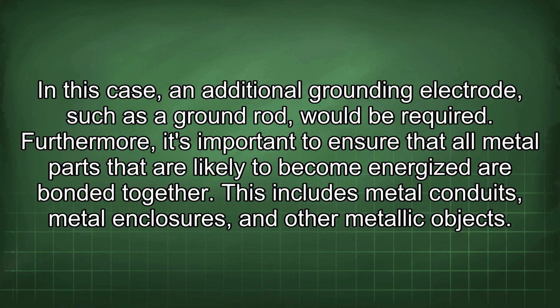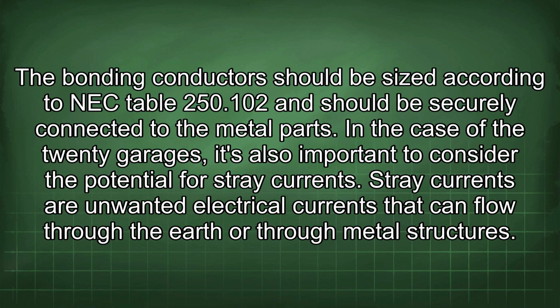Furthermore, it's important to ensure that all metal parts that are likely to become energized are bonded together. This includes metal conduit, metal enclosures, and other metallic objects. The bonding conductors should be sized according to NEC Table 250.102 and should be securely connected to the metal parts. In the case of the 20 garages, it's also important to consider the potential for stray currents. Stray currents are unwanted electrical currents that can flow through the earth or through metal structures.